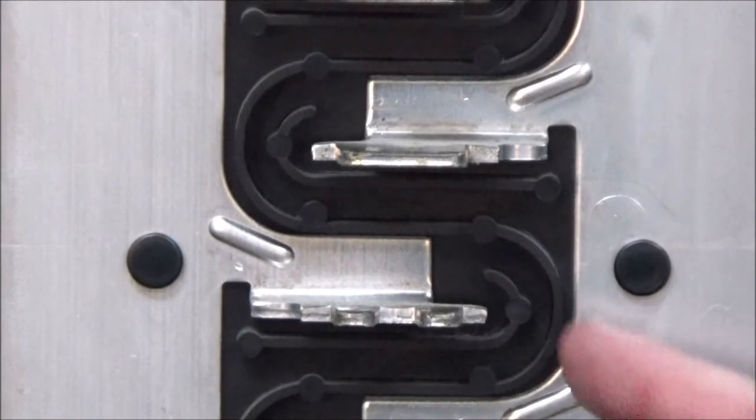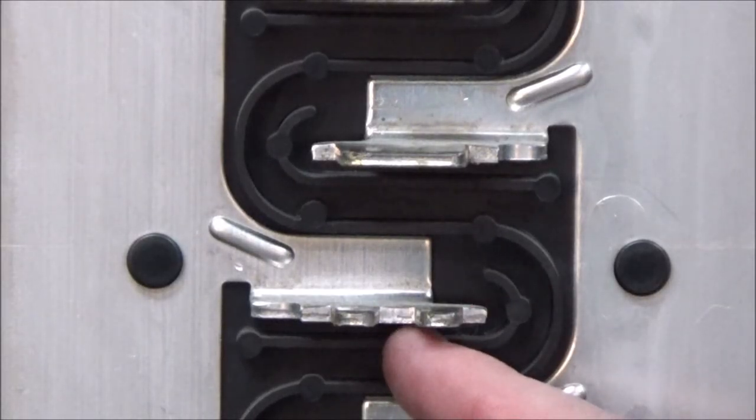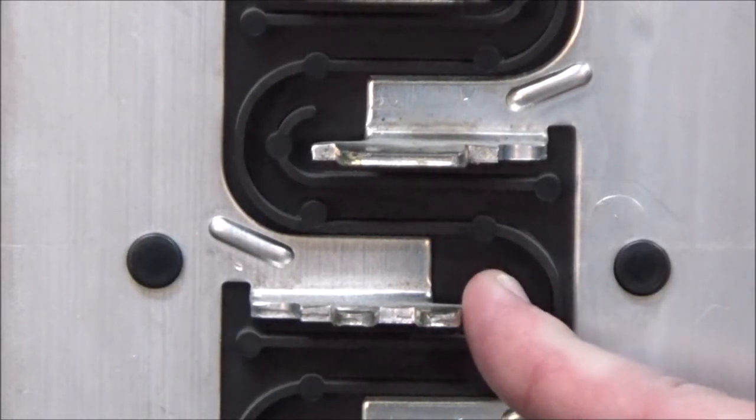You will see that this spot has a notch in the center. If the spot has a notch like that then the space will accept a tandem breaker.